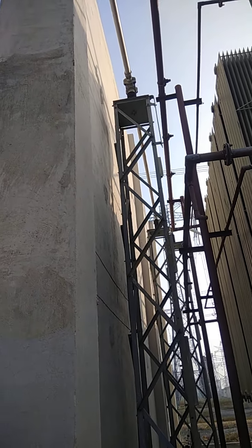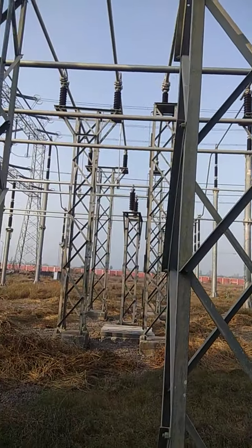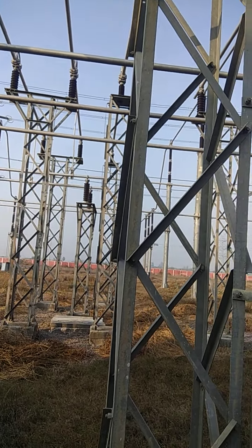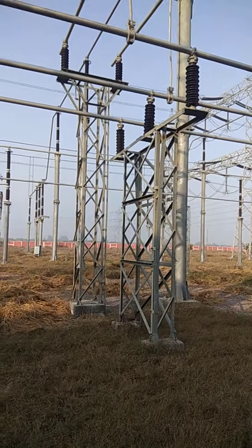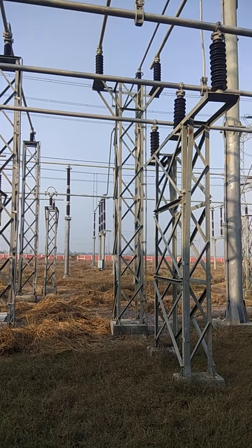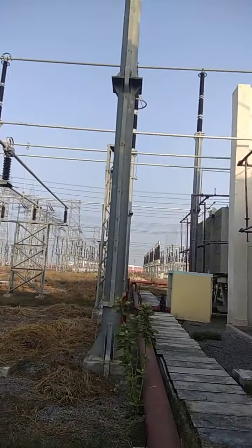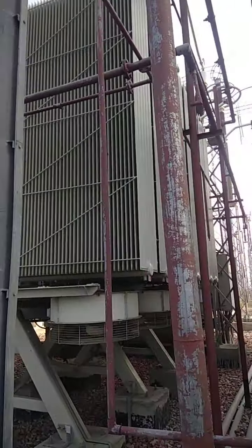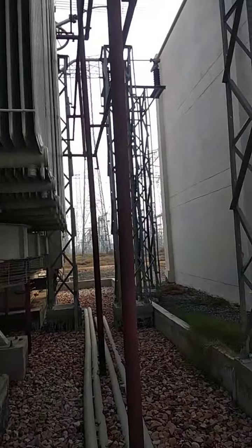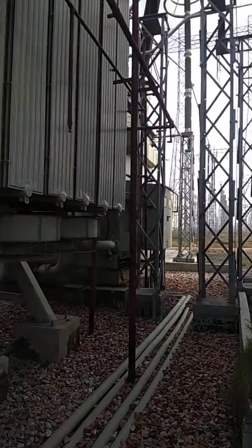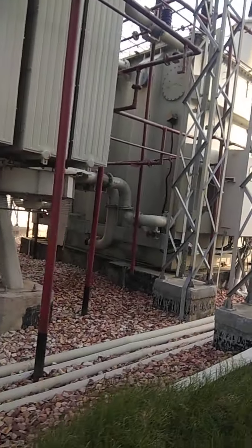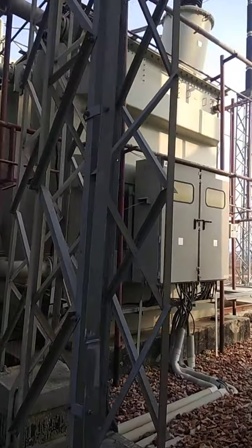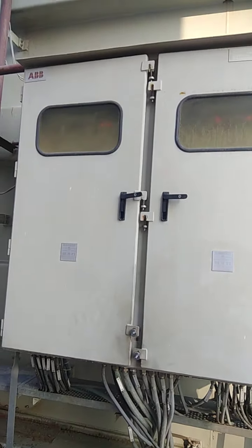This is the neutral bus arrangement of a single phase unit. It is combined on a neutral bus there. We made the Y phase the master for OLTC, and the command to change the tap changer comes to the master, then it goes to the slaves.